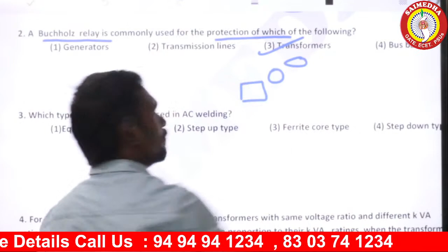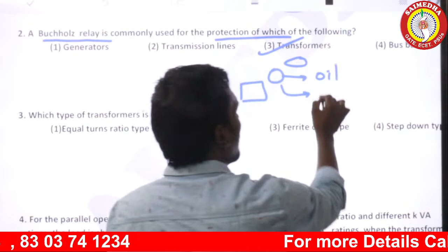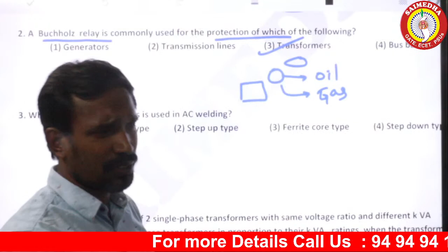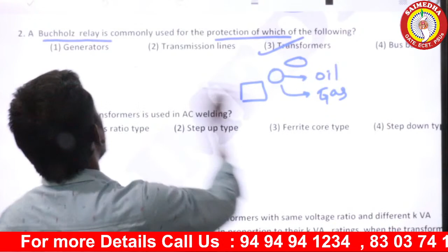Buchholz relay is connected between the main tank and conservator tank, and is generally used in oil immersed transformers. But Buchholz relay is a gas activated relay, not an oil activated relay. We know this generally, so option 3 is the correct answer.